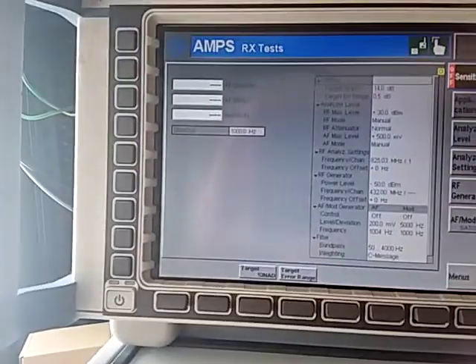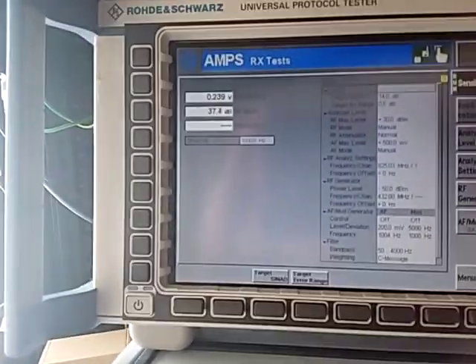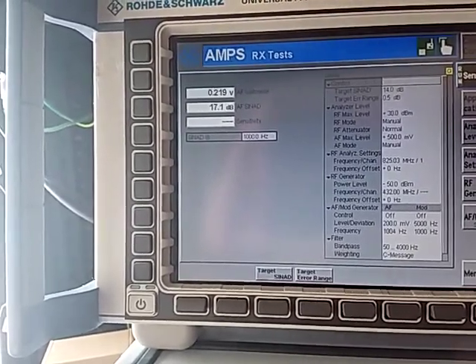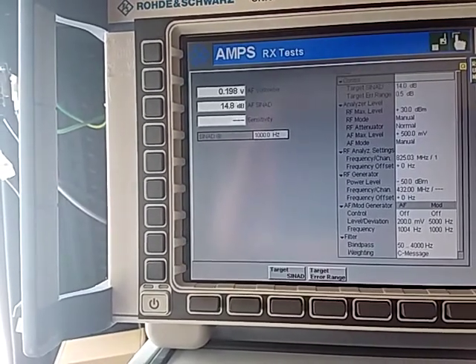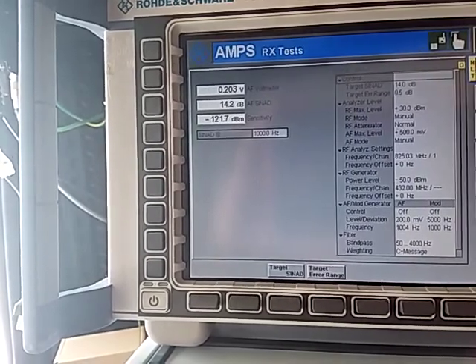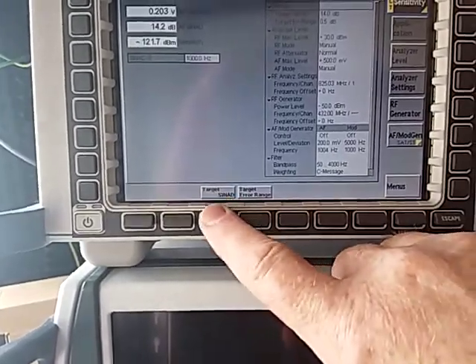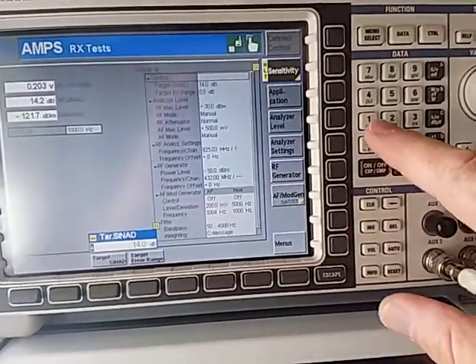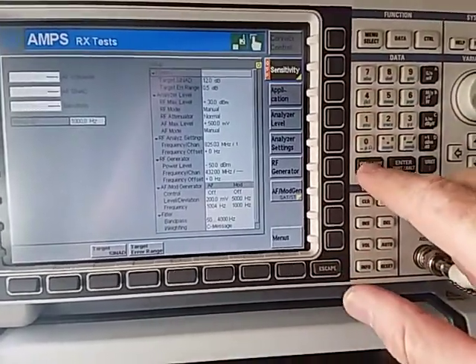But you may want to know what the sensitivity at 14 dB SINAD is. So you simply type 14 in and restart the test. It will run away and automatically test and come back with the output level: minus 121 dBm for 14 dB SINAD. So we can change that back to 12 dB SINAD and run our test again, which gives us minus 122 dBm.